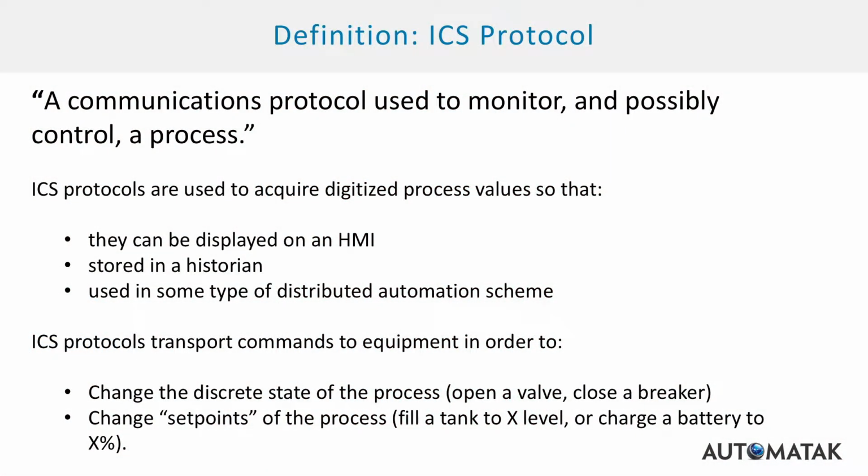Why would you deploy these protocols? Well, typically, they're replacing those analog things that Marty talked about, like using pressures to signal value levels, or 4-20 milliamp control loops. We're now replacing those things with networked digital equivalents so that we can use those protocols to get those values up to our human-machine interface, so we can store them in a historian, so we can later look at what the process has been doing over time.